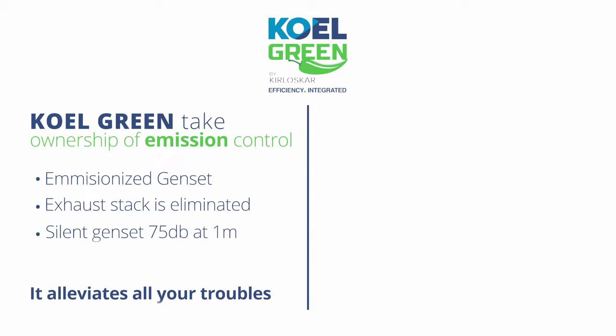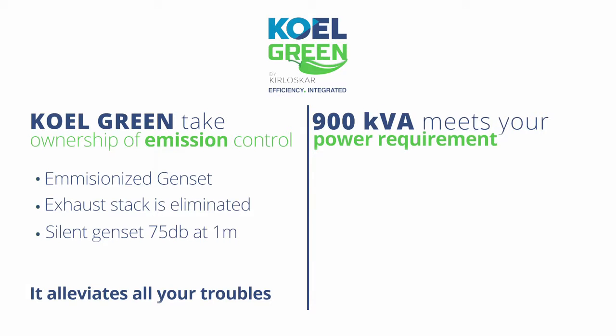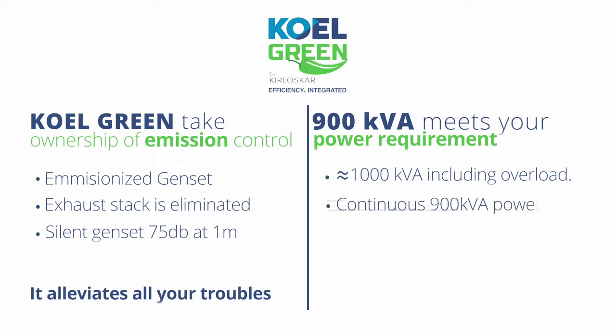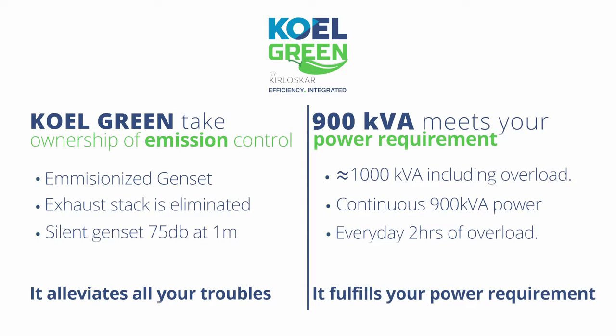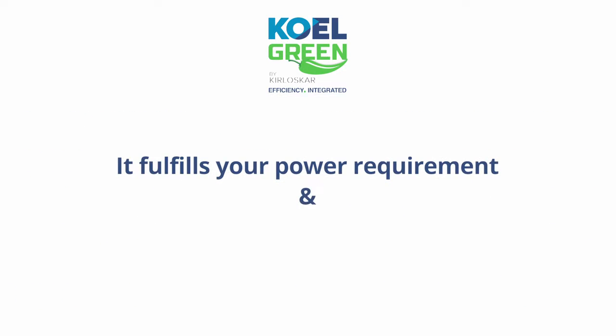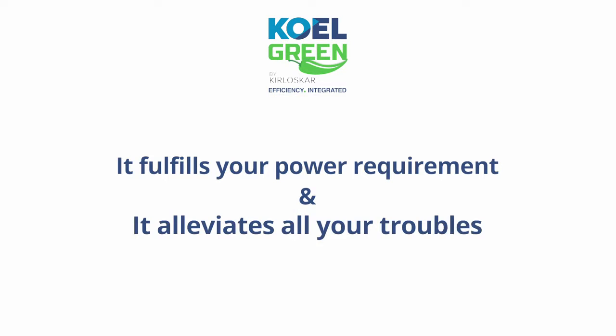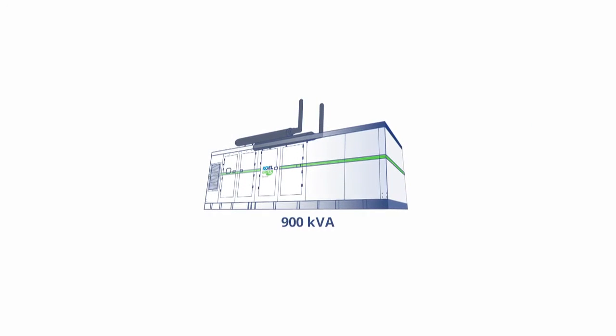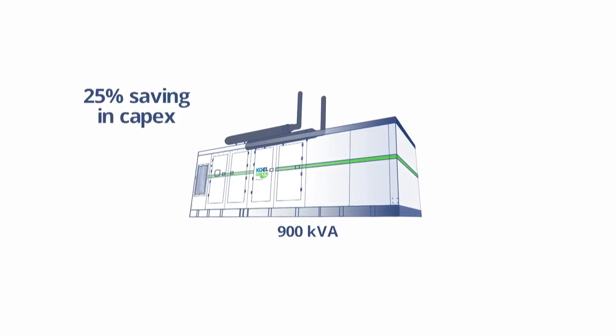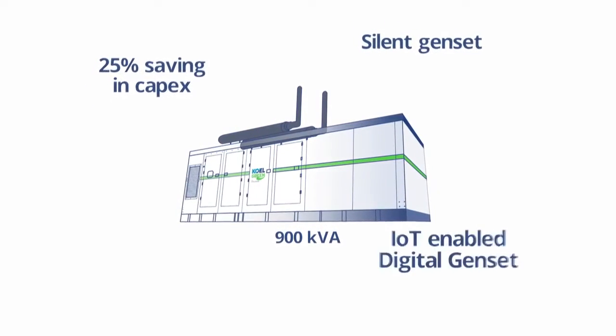At the same time, the 900 kVA genset has a 10% overload capacity. This means, as per standard, every day 2 hours of loading of 1000 kVA is possible on this genset. Which means this genset meets your power requirement and at the same time removes all the extra effort and expense of using 1000 kVA.